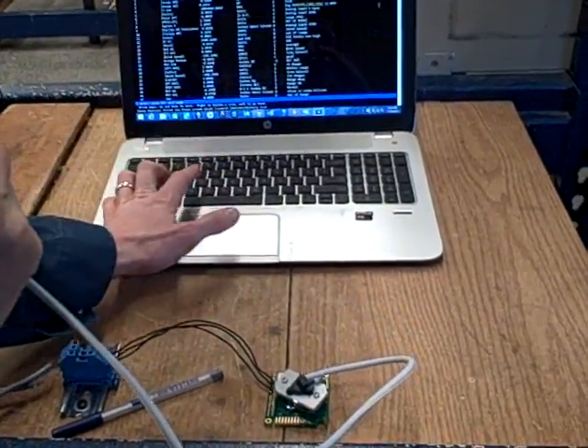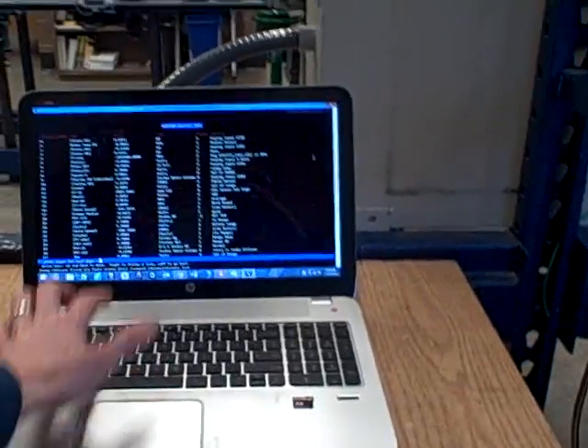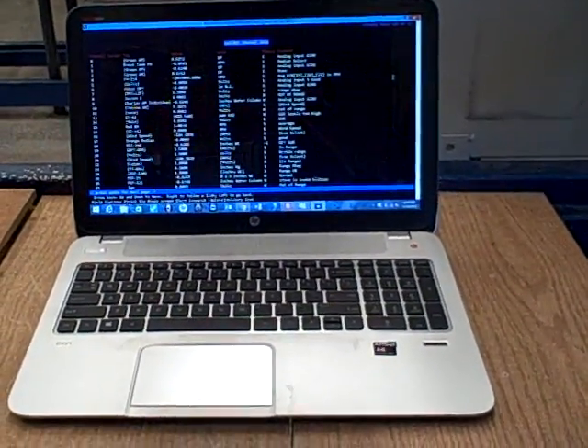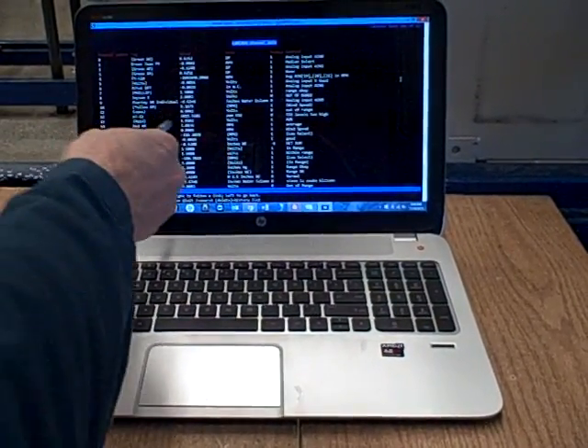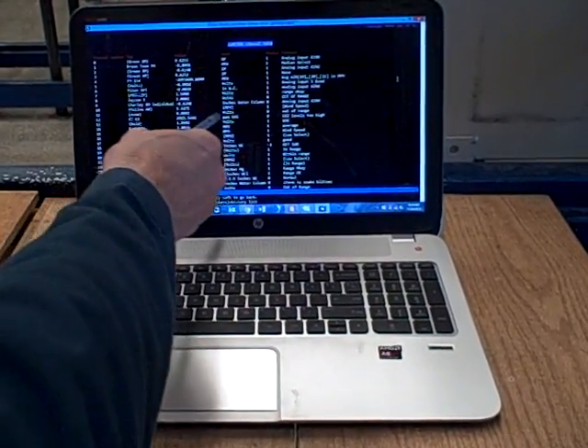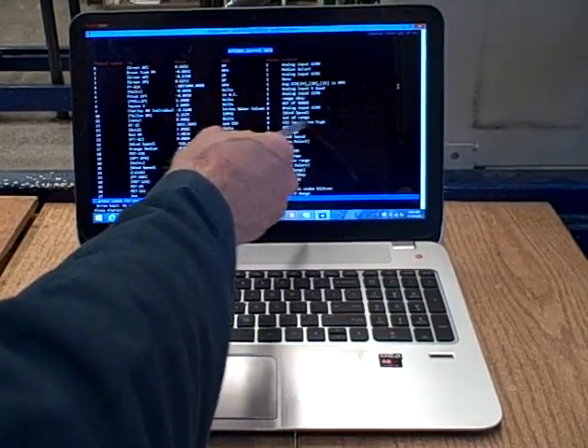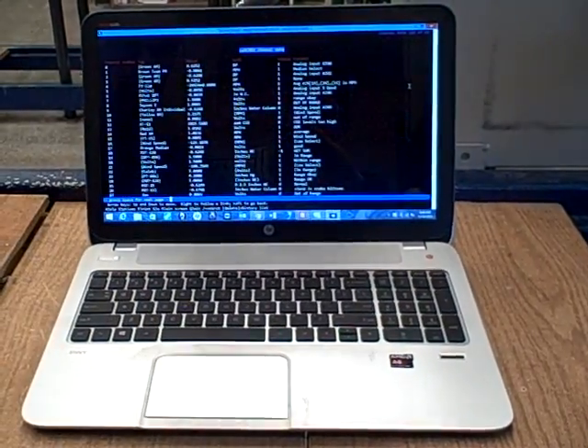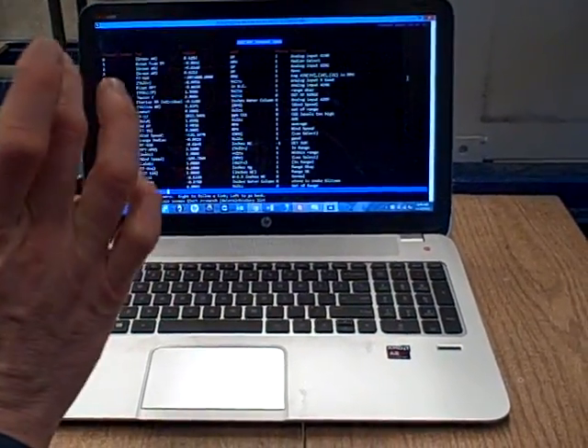It's up over 1,000 ppm. There's 2,000. We're basically full range right now, and we've got our SCADA system programmed so above a certain threshold it reads CO2 levels too high. It's got to come within a fairly narrow range to read normal again.